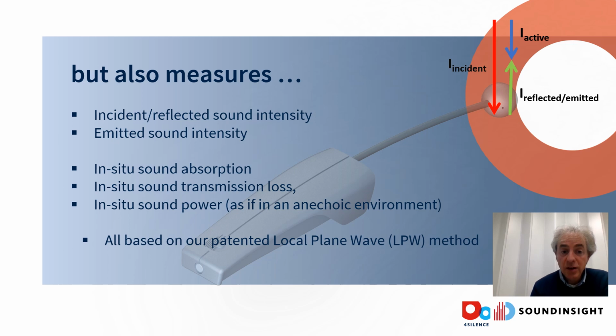So that having said, we can measure in situ sound absorption in a sense that we do not depend on any global sound field or known sound field that we impose. We can also measure in situ sound transmission loss and in situ sound power as if you would be in an anechoic environment, but that will come later. And all this is based on our patented local plane wave method that we invented to come up with this separation.